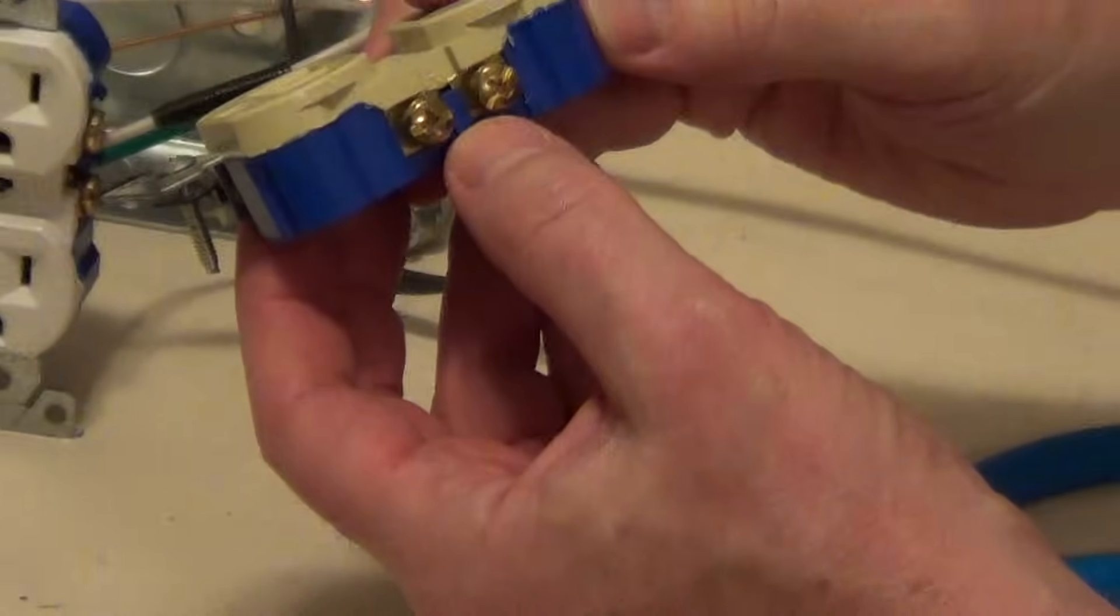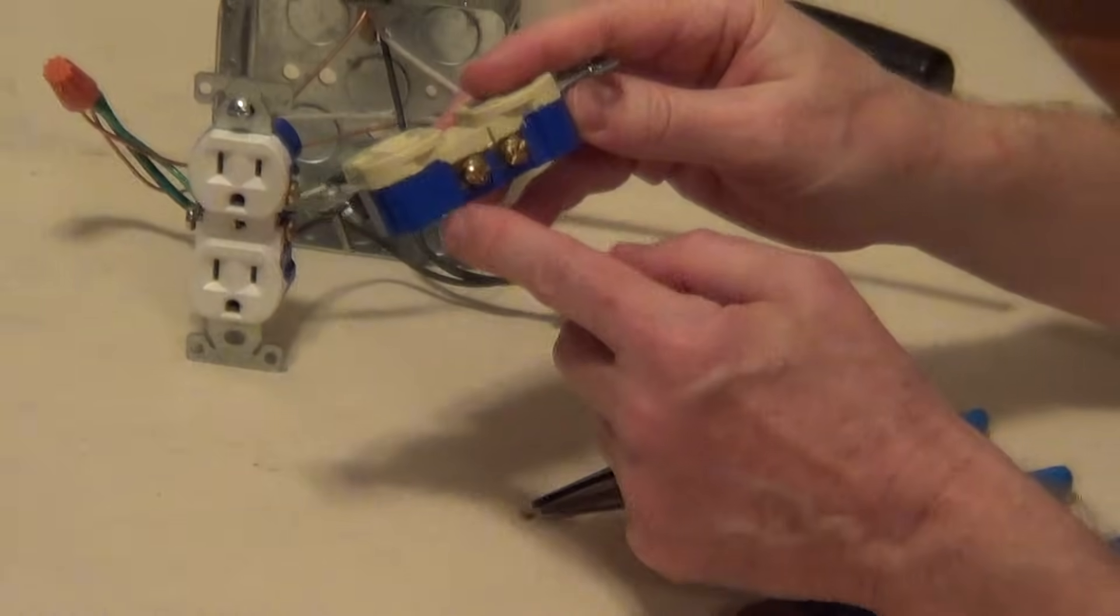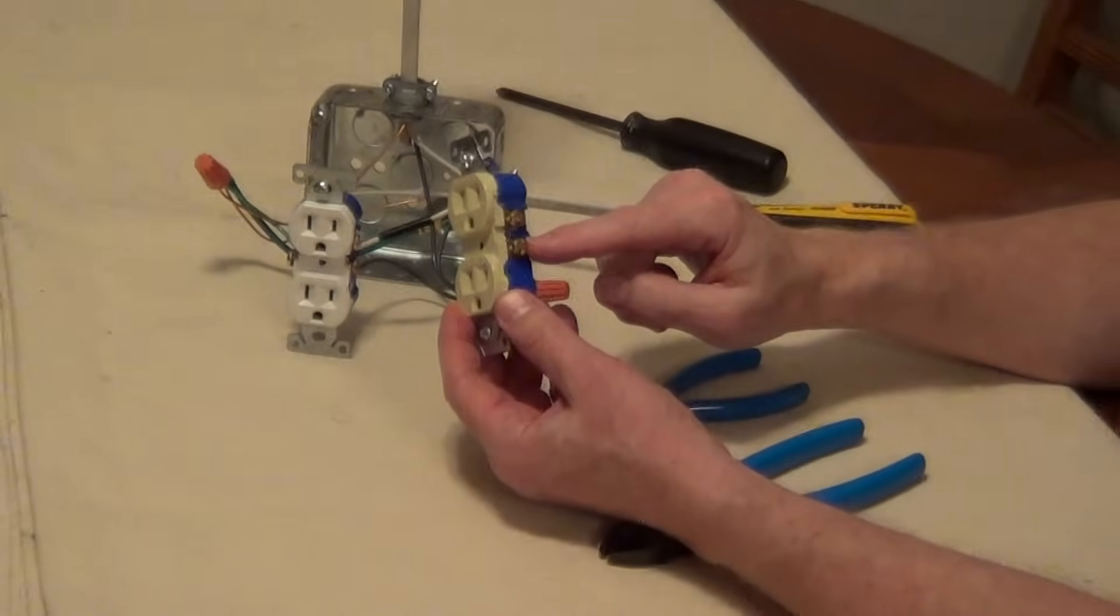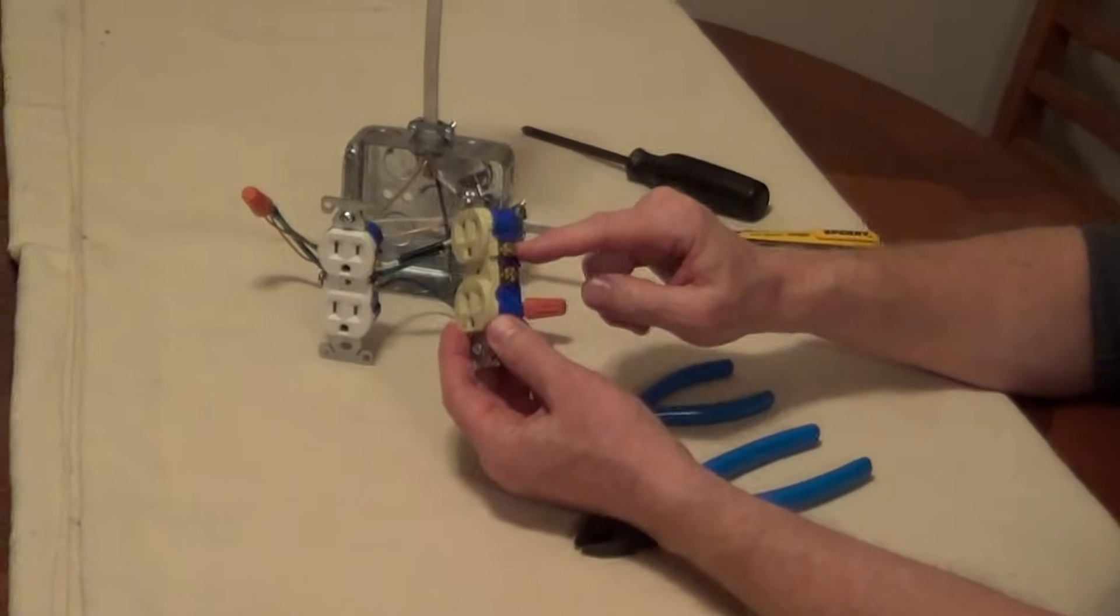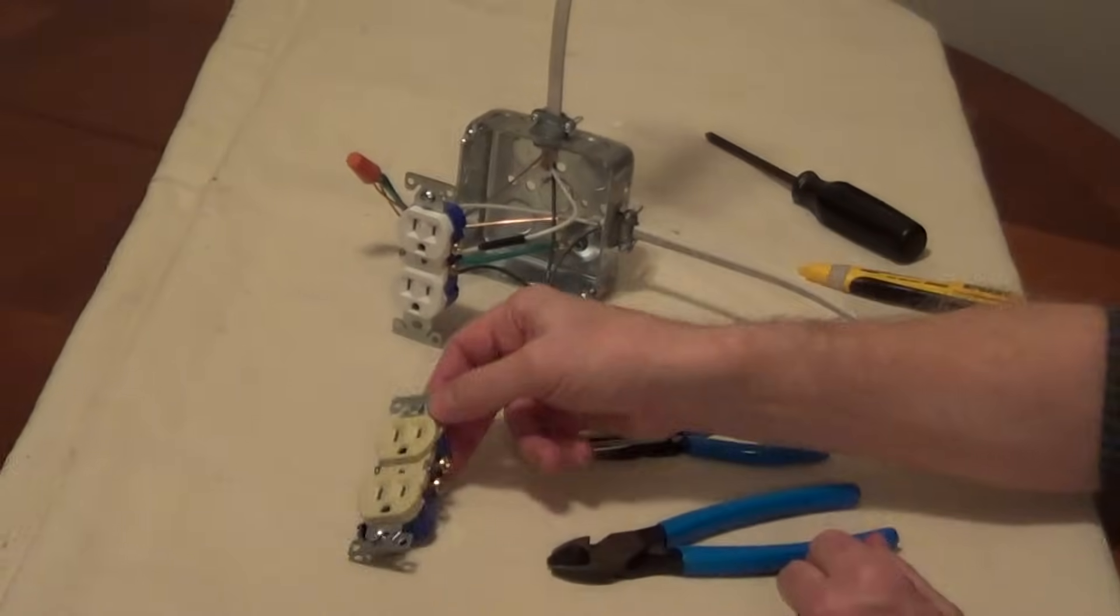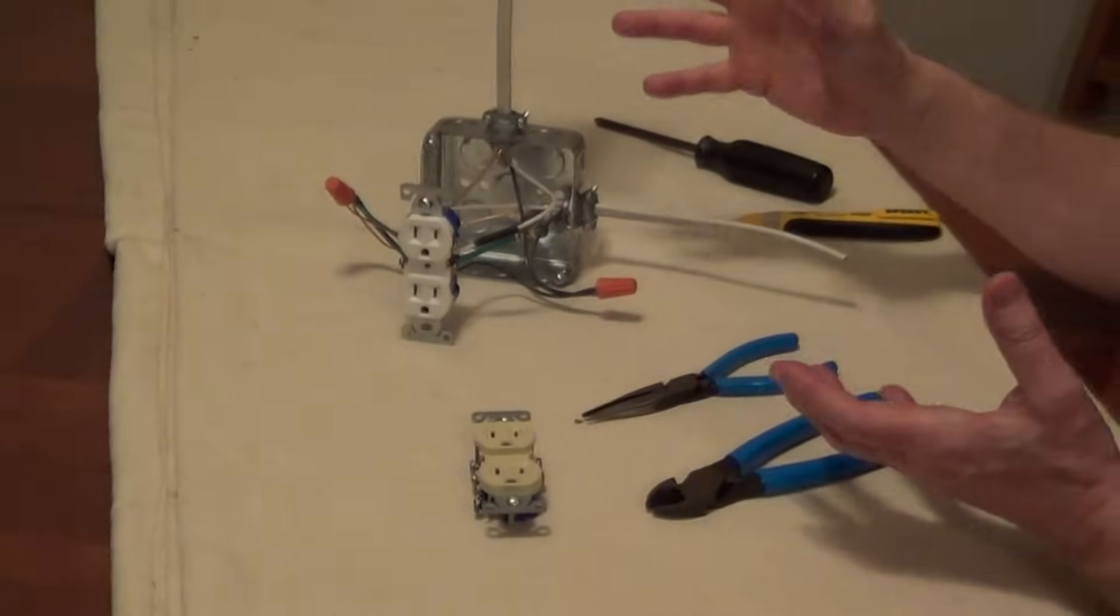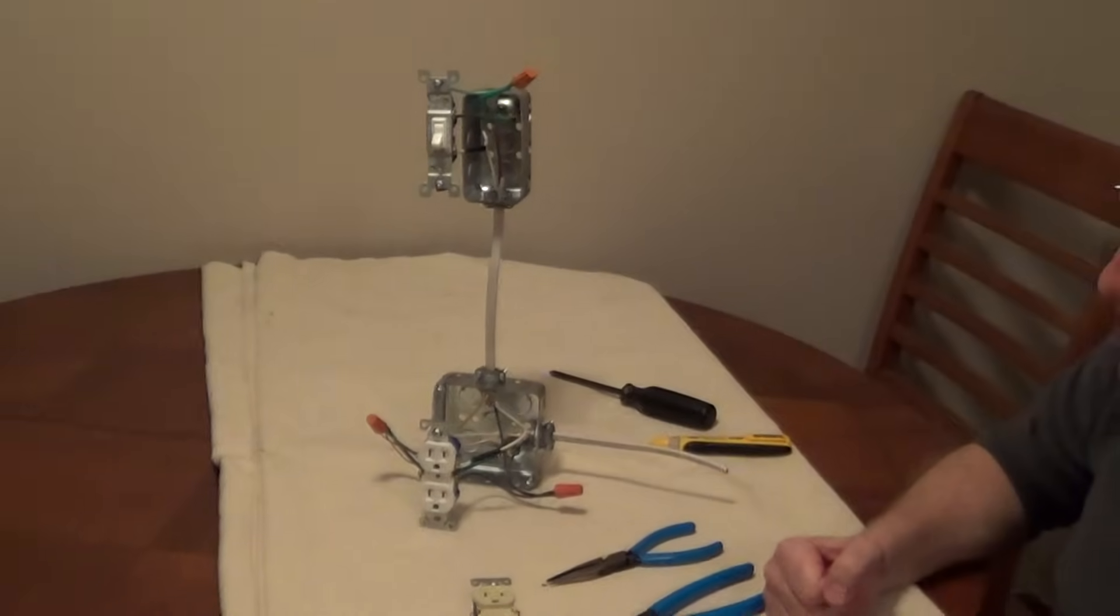And now these are completely distinct. They're separated, so we can have one hot that's always going to be on on the bottom and then our hot on top is controlled by the switch. So very simple to do, and that's the wiring scheme for a switched outlet.